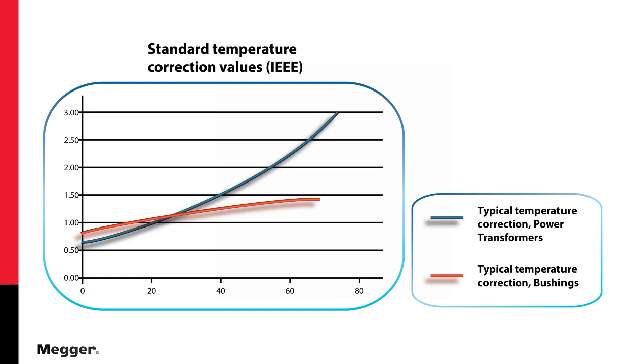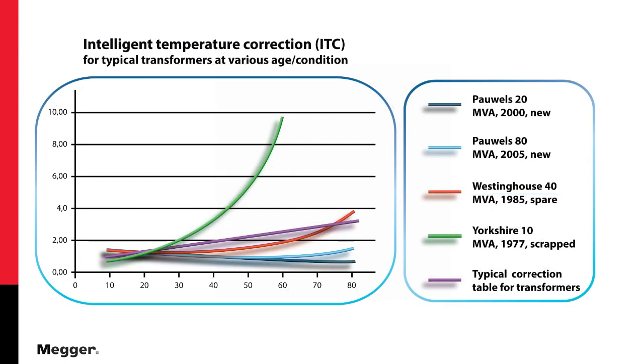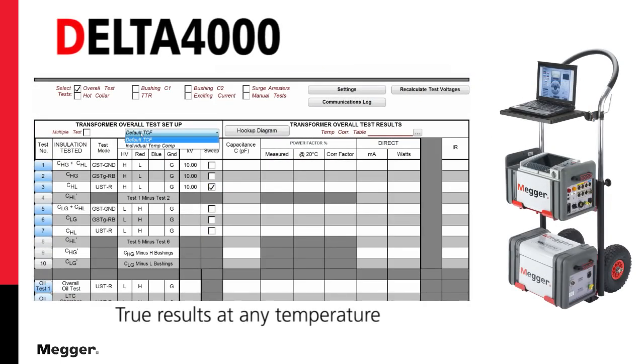Temperature correction graphs place all transformers and bushings into one or two categories, which is not accurate for many of our critical assets. As can be seen by this sample of actual temperature correction for various transformers, results can vary significantly. With the Megger Delta 4000 and its patented intelligent temperature correction feature, we are now confident that the results are true at any temperature we test at.